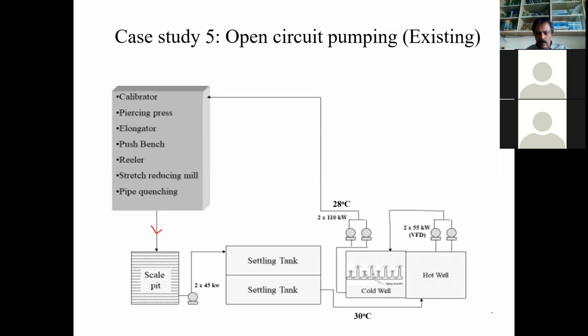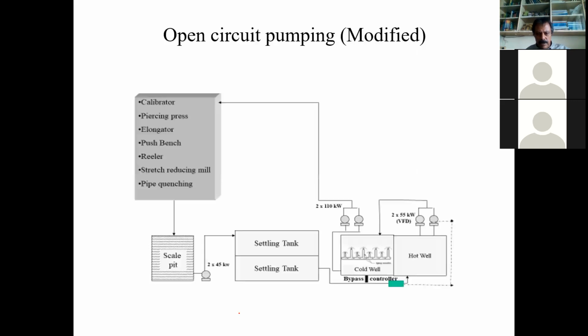Here, as you can see, the hot water was coming at 30 degrees from the process, and cold water going at 28. After modification, we provided a bypass here with thermostatic control. The water will come here. When it is greater than 34, it will go to the hot well. When it is less than 34, it will bypass to the cold well and directly get pumped into the process. So it keeps on circulating, and when the water becomes 34, it goes to the hot well. Otherwise it short circuits into the cold well directly. So these 2 into 55 kilowatt pumps, we don't need to operate continuously.